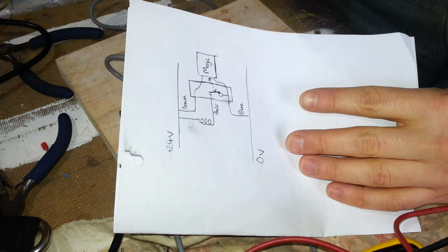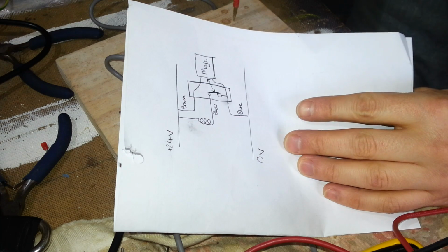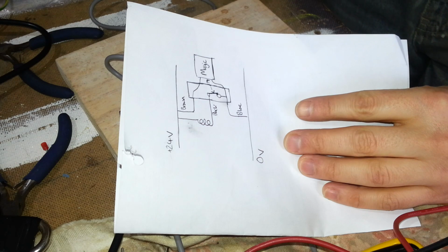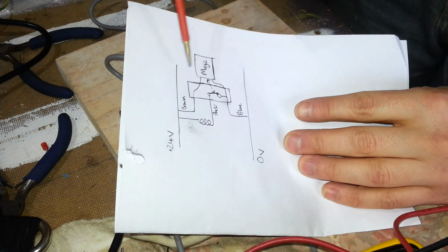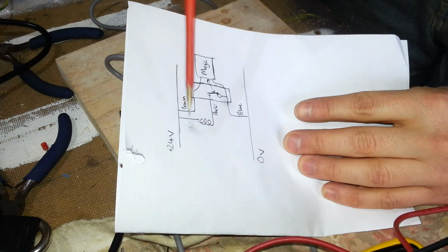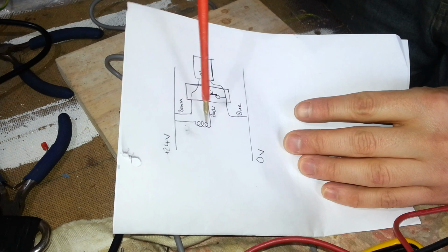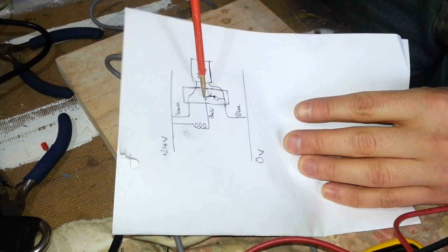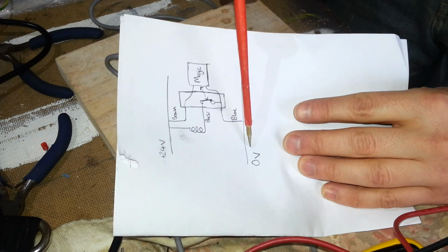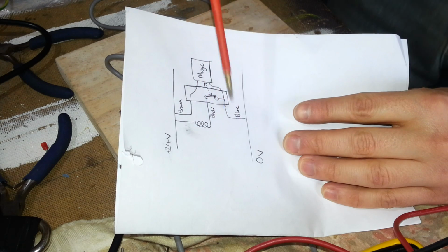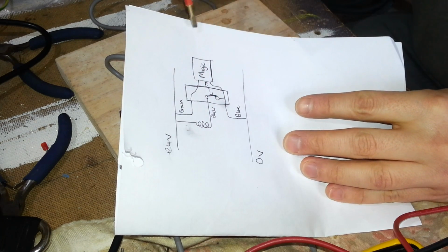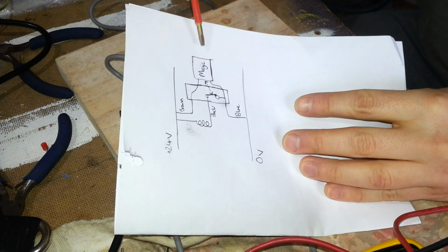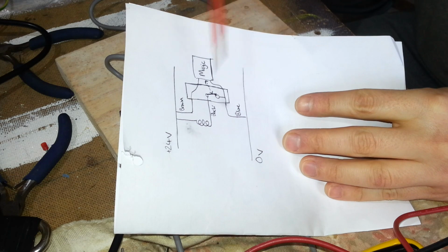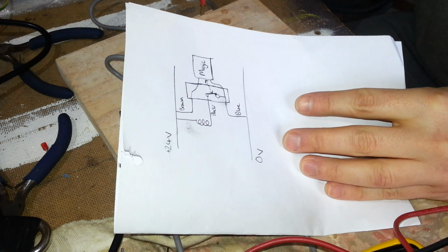Now, it's not a mechanical switch, it's an NPN switch, three layers of doped silicon, and they electronically switch that circuit. So you can see at the moment, in its standard state, with no metal anywhere near it, current will flow down here through the coil and along the black load wire, and then down through the switch and out through the blue wire. Thus, in this case, pulling the relay closed. When a piece of metal comes in near to the sensor, this switch will be pulled open, the coil will de-energize, and the relay will switch. And it's as simple as that.